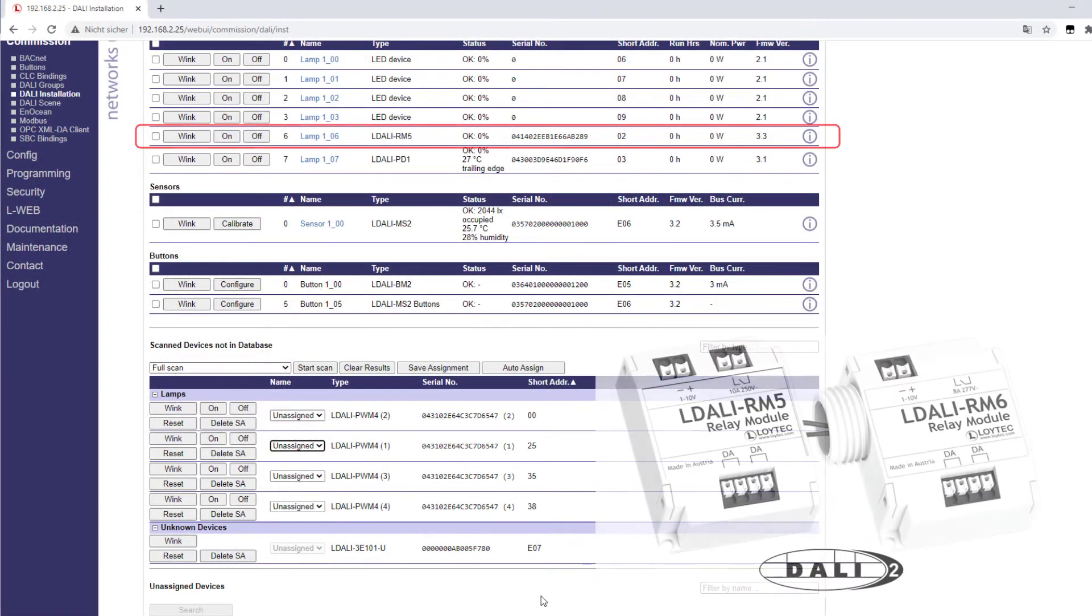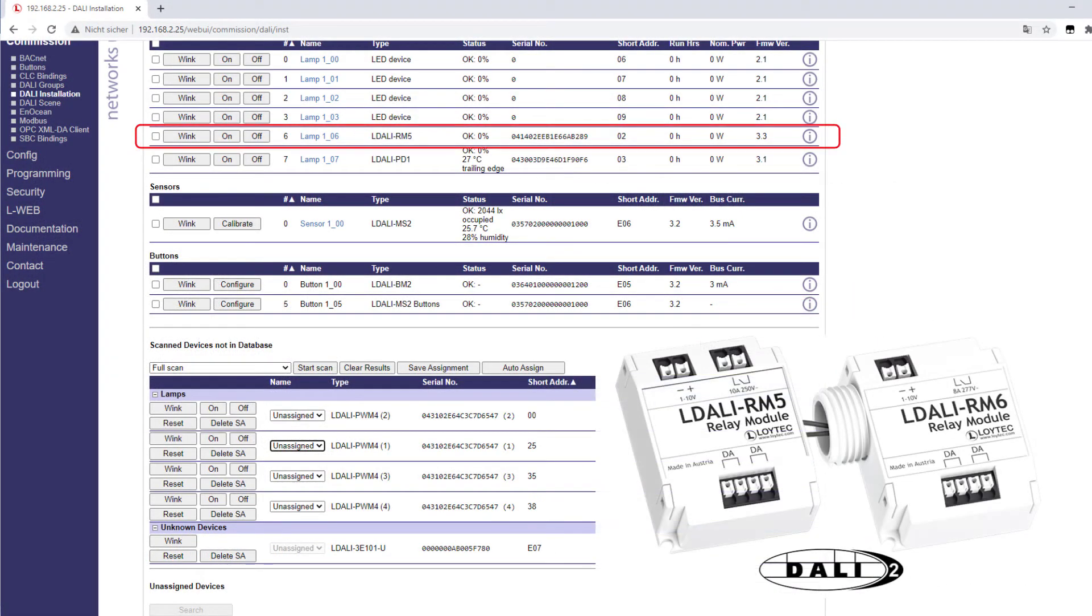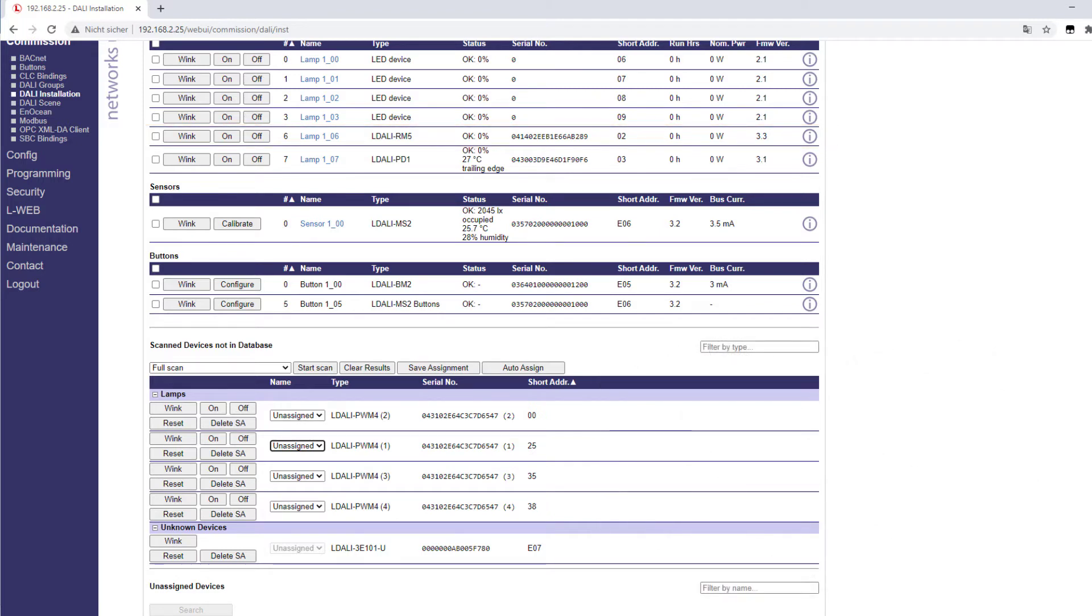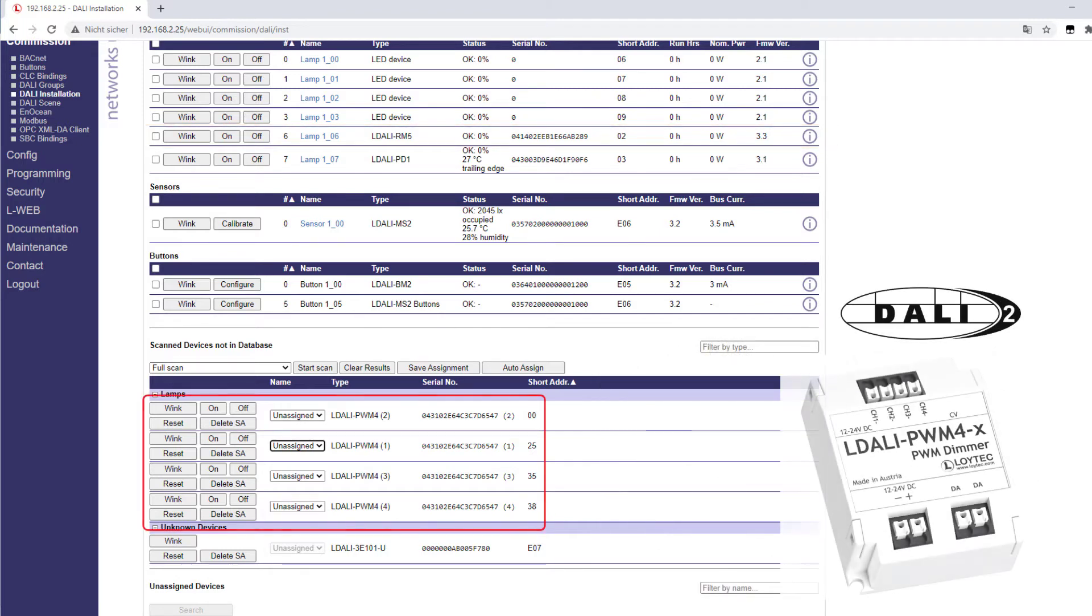The L-DALI controller now supports the Loytec devices L-DALI-RM5 and L-DALI-RM6. These modules can either be used as simple relay modules or as converters for ballasts with a 1 to 10 volt interface with a maximum output current of 50 milliamps. Support has been added for the L-DALI PWM4, a constant voltage LED driver with four output channels, each of which can be controlled via a separate DALI address. It can handle 12 to 24 VDC.